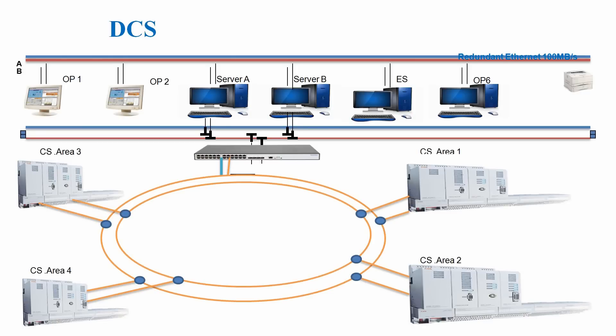So what is DCS? DCS, or distributed control system, is a control system for a process plant where control elements or controllers are distributed in the network or in the system. In this particular diagram, we have different areas and in each area we have different controllers. Area 1 has its own controller, area 2 has its own, area 3 has its own controller. All these controllers are on a fiber network connected to a particular switch, and that switch is connected to the LAN network.